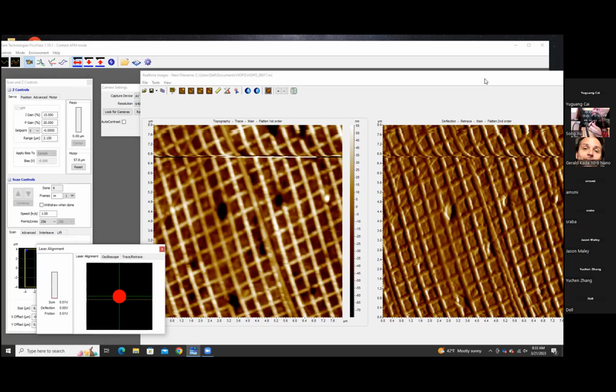4.96. 4.96. Okay. So they're not going to be 100% spot on every time that you do this, because you've got to factor in things like how well your DC multimeter is calibrated, right? That could cause deviations in your measurements. Just make sure that you're relatively close. And when I say relatively, 4.9 is relatively close to 5. If you're at 4.3, you've probably got a problem.